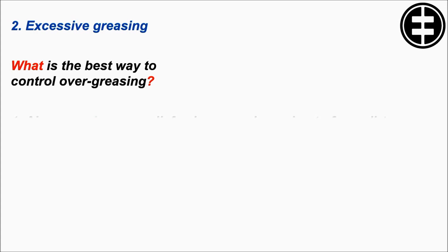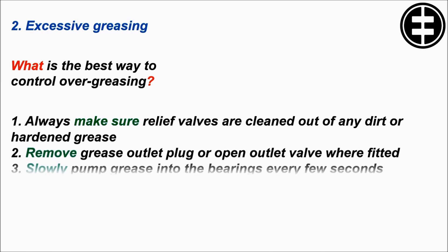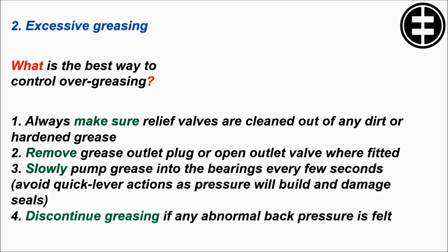What is the best way to control over-greasing? One: Always make sure relief valves are cleaned out of any dirt or hardened grease. Two: Remove grease outlet plug or open outlet valve where fitted. Three: Slowly pump grease into the bearings every few seconds. Avoid quick lever actions as pressure will build and damage seals. Four: Discontinue greasing if any abnormal back pressure is felt.